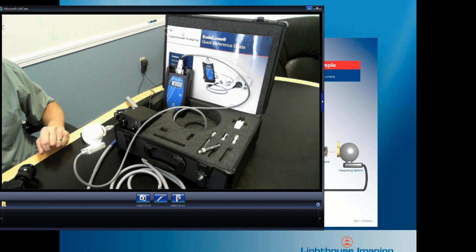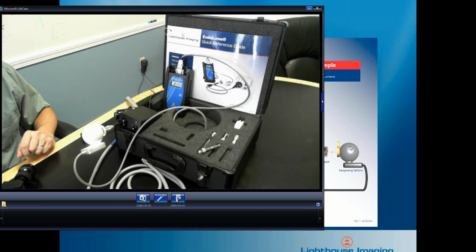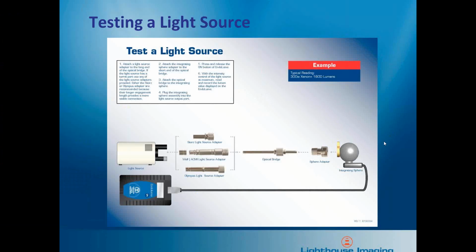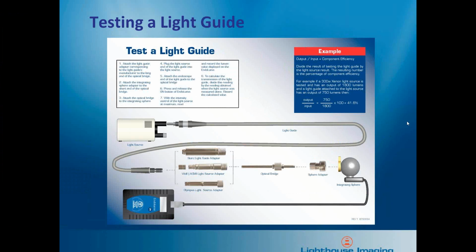So that's our baseline. If we flip back to the presentation here momentarily and go to the next slide, we'll see that it shows you how to test a light guide. Again, the setup's very similar. We use the light source. We plug the light guide into the light source, use the correct fitting, always using the optical bridge because it's part of the calibration procedure for the EndoLume, sphere adapter, and into the sphere.